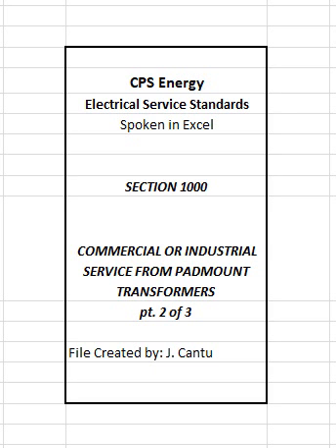1. Open access to transformer both vertically and horizontally by equipment and personnel. Where located behind a wall or fence, the wall or fence may not be taller than 8 feet and must include a minimum 10-foot wide opening in front of transformer. 2. A 15-foot wide, all-weather drivable surface up to transformer slab for access by CPS Energy crane. Drivable surfaces shall meet the design criteria outlined by CPS Energy's underground engineering section.